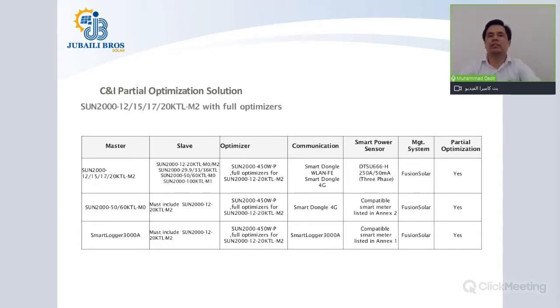C&I partial optimization. Partial optimization, speaking of this terminology itself, is a type of requirement in a PV project where you are using an area which is partially shaded at some time of the day, and the rest of the time it may have adequate sunlight to get the benefit and generate PV output. In those scenarios, in order to optimize the use of space, you might use a power optimizer. Power optimizer and its applications: where you want to use a space which is shaded, maybe due to the shade of a nearby building, a nearby tree, or similarly clouds, you can use the power optimizer. So in this scenario, again we have three different sections.